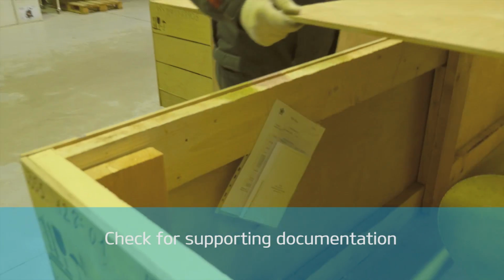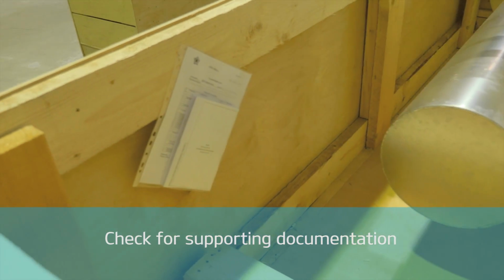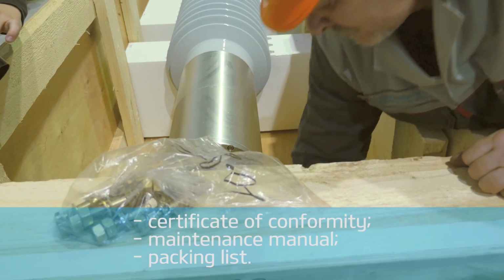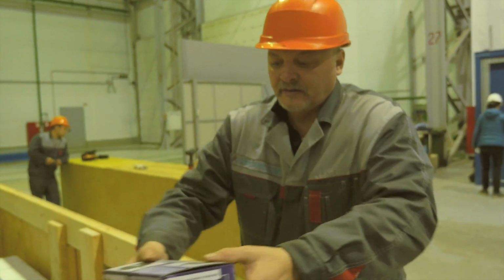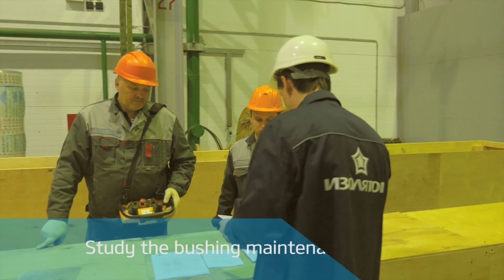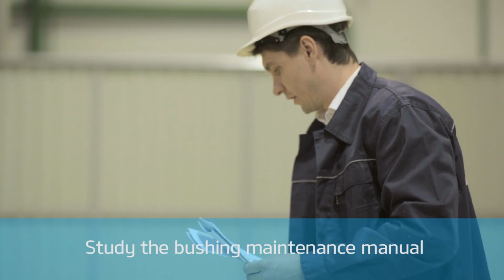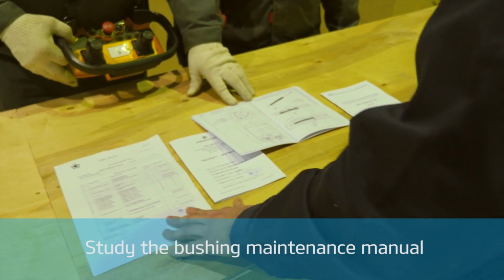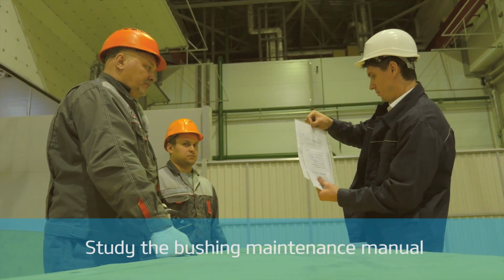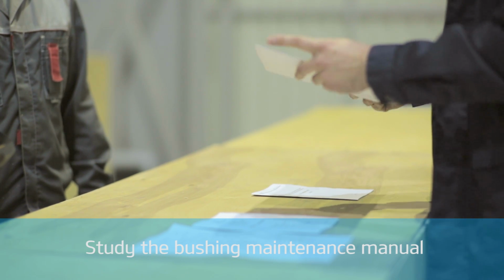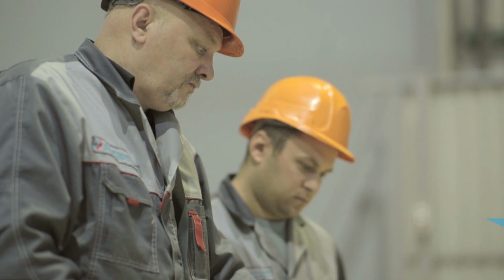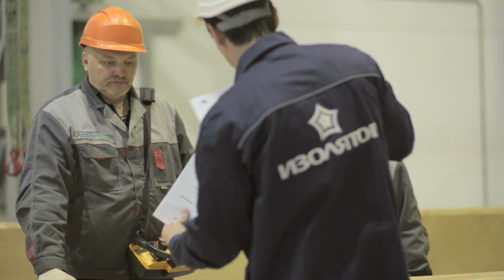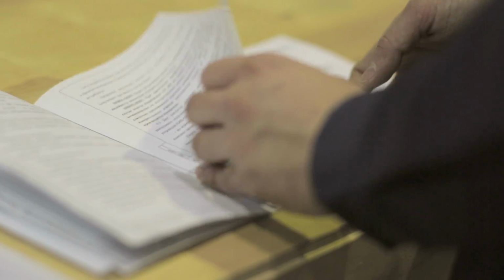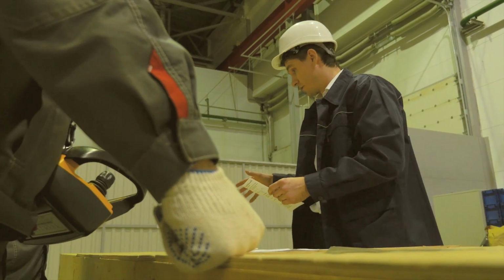Check for supporting documentation, which should be attached to the packaging side. It includes Certificate of Conformity, Maintenance Manual, Packing List. Please verify the completeness of the bushing set against the packing list. Study the bushing maintenance manual. It contains all main operations including removal from the packaging, installation in a transformer, and operational maintenance. The plant warrants that only with the manual requirements fulfillment a high-voltage bushing will operate reliably and fault-free throughout its entire service life.